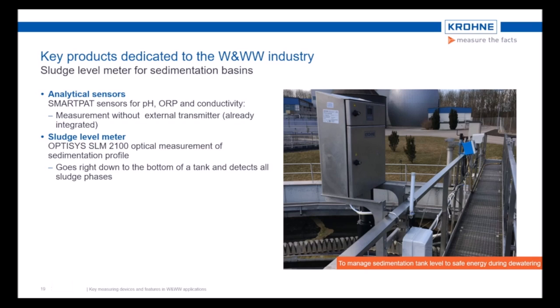Compared to ultrasonic, which is an indirect measuring because it is beaming from the top, this is a direct measuring directly within the process. So with knowing the sludge concentration over the complete tank profile, you can easily increase the efficiency of your process due to the higher fillings and the resulting higher gravity thickening. You therefore need less energy for the mechanical dewatering of the sludge, which saves pure money.